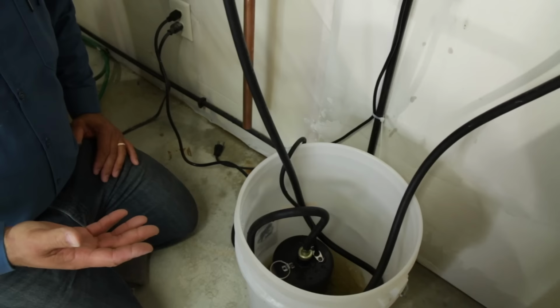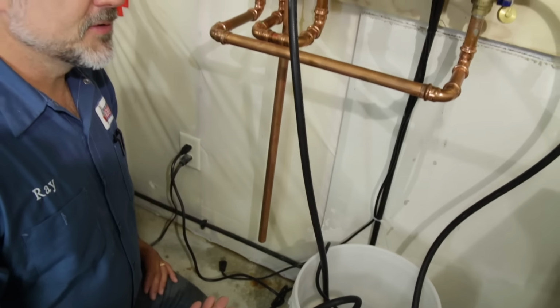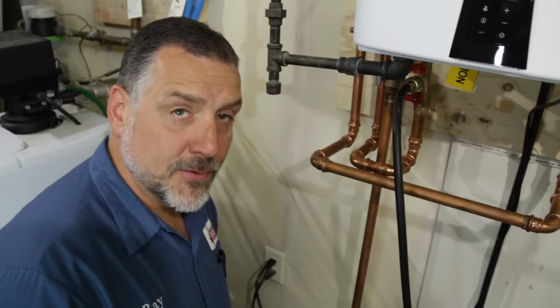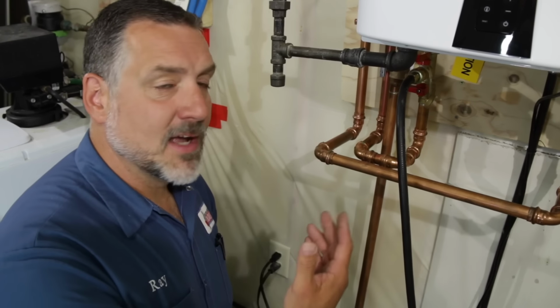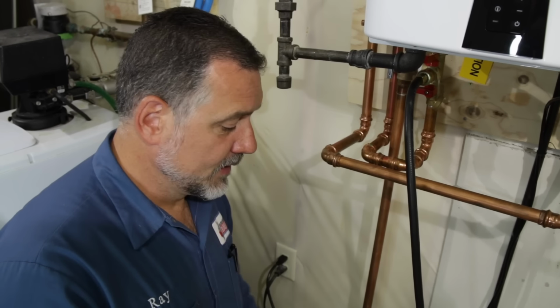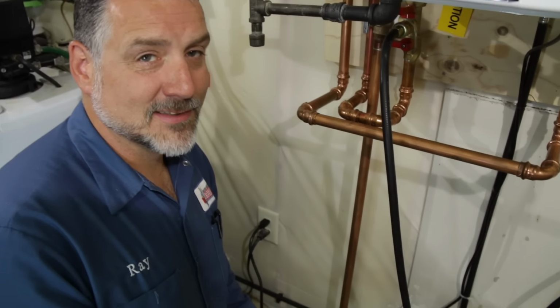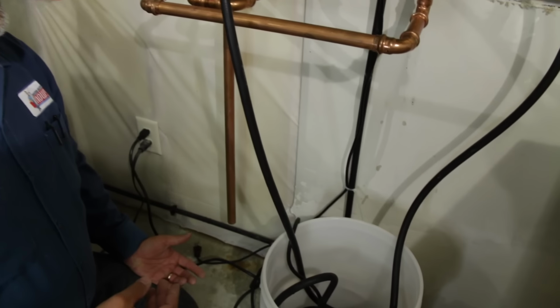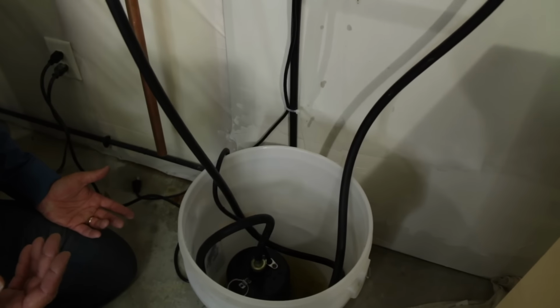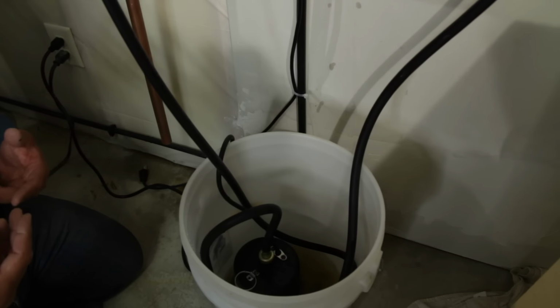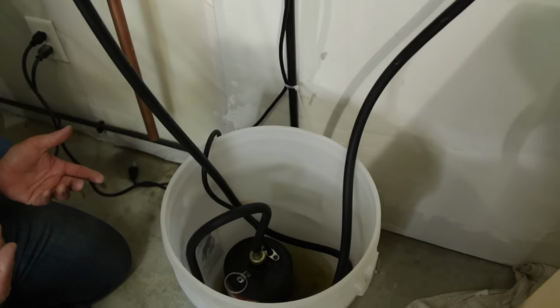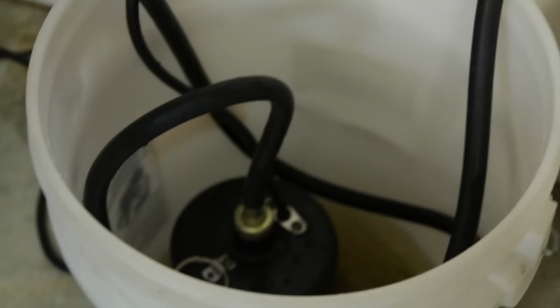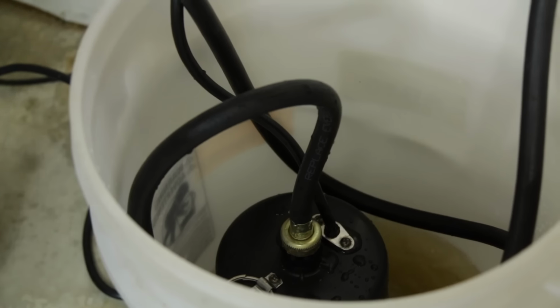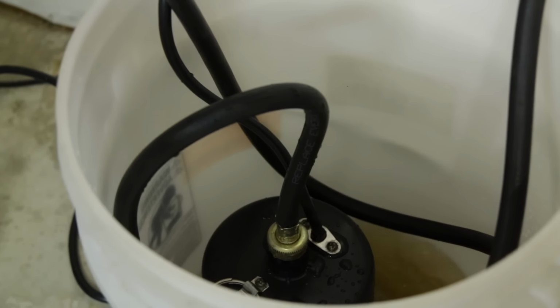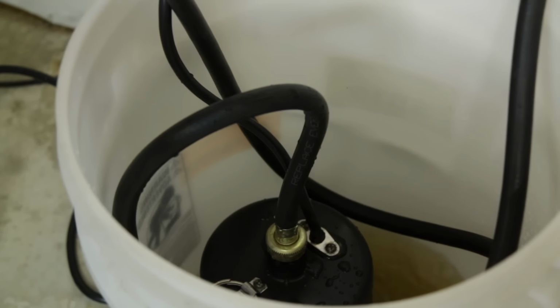You see in the bucket, vinegar is being pumped up through the sump pump, running through the heat exchanger, and then coming out the hot water outlet. If you notice the color of the water, it doesn't look like clean vinegar anymore. That's the scaling we see in the heat exchanger being cleaned off. If we leave this running for half an hour, and if this is done annually, your heat exchanger will stay a brand new stainless steel look on the inside.